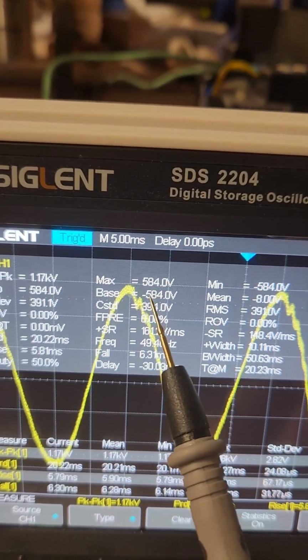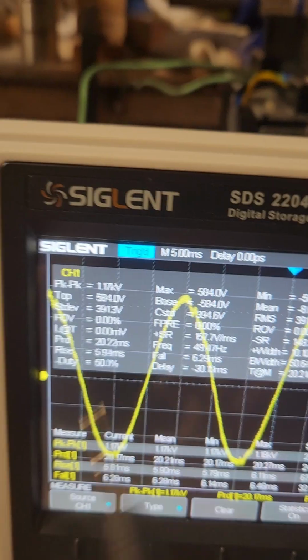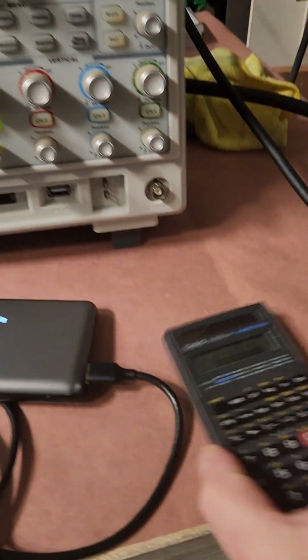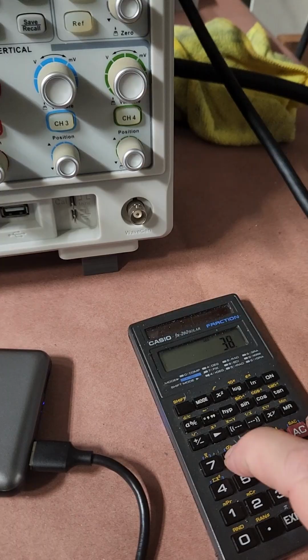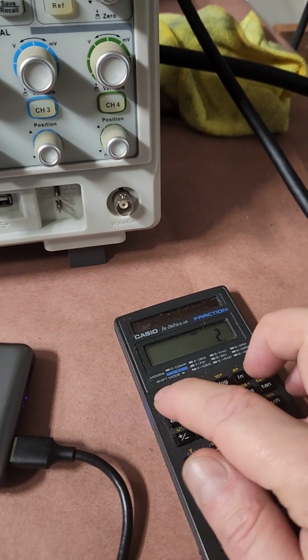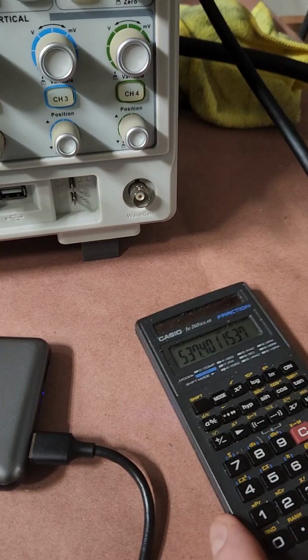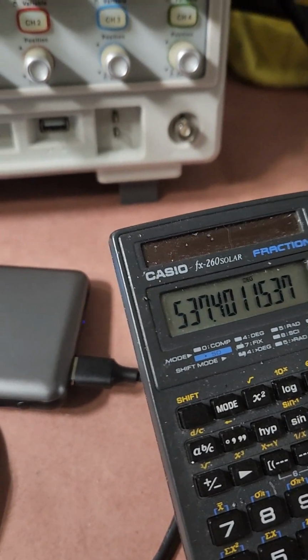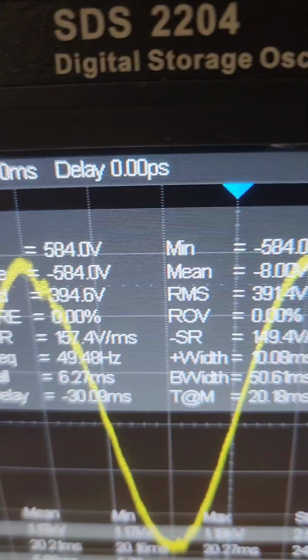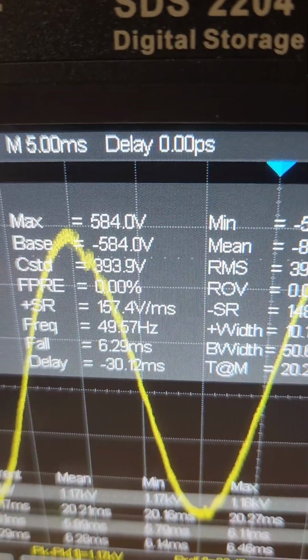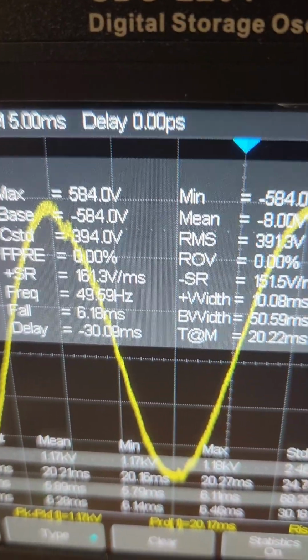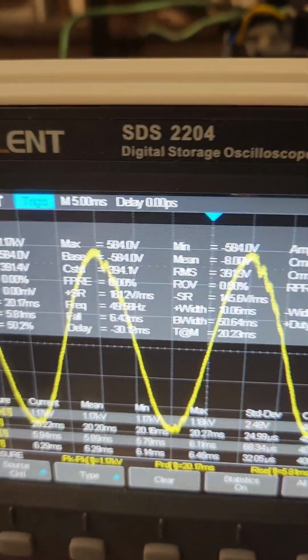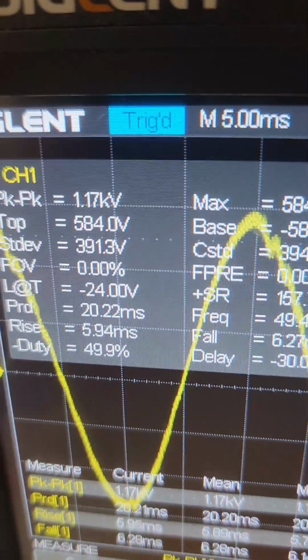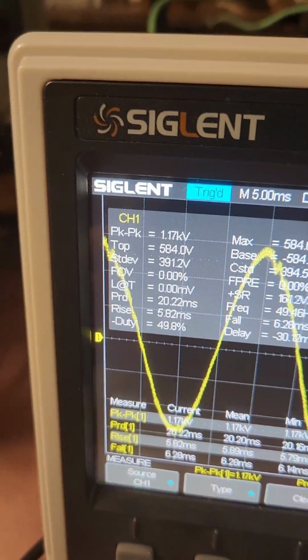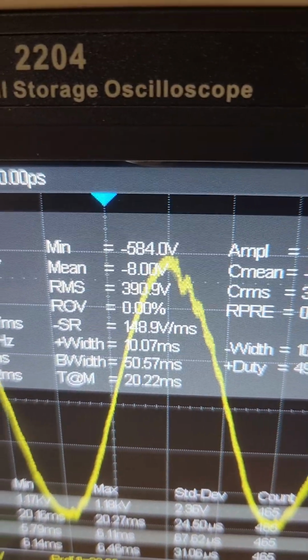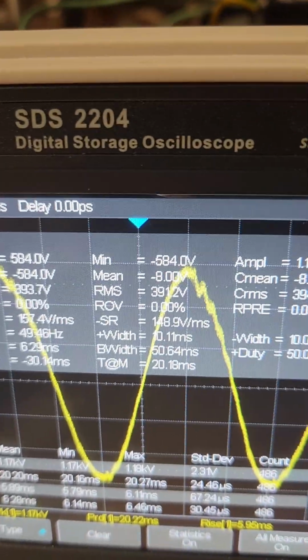What bothers me is this max voltage, 584. Because usually when you have 380 volts, multiply by the square root of 2, it should not be more than 537 volts. But I get max there is 584. So 584 versus 537, that's 8% more. The peak to peak you see there is 1.17 kilovolts. And RMS here is 390, 390 versus 380.